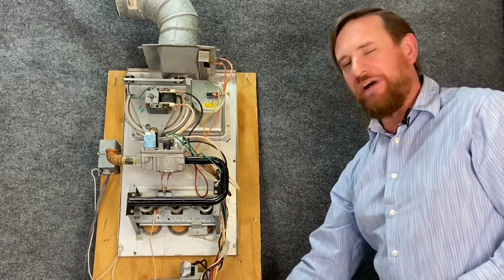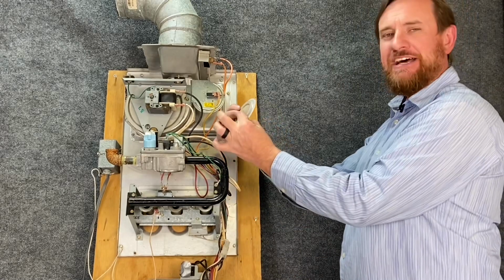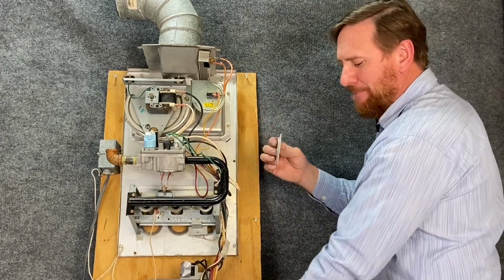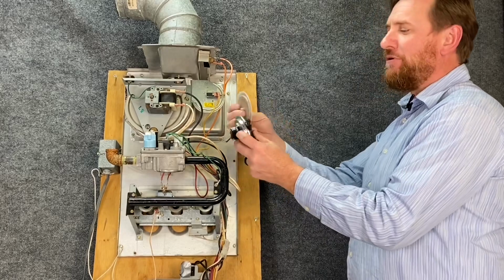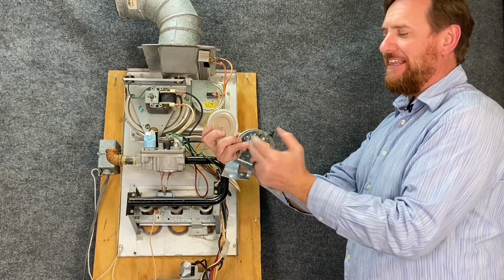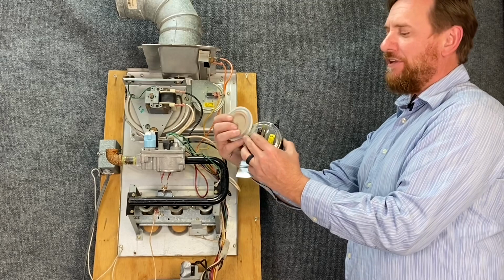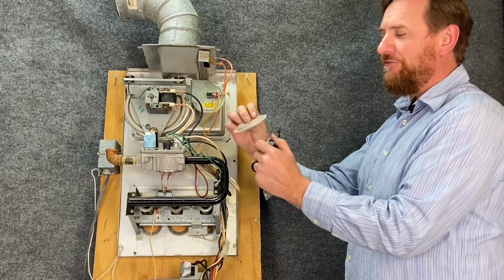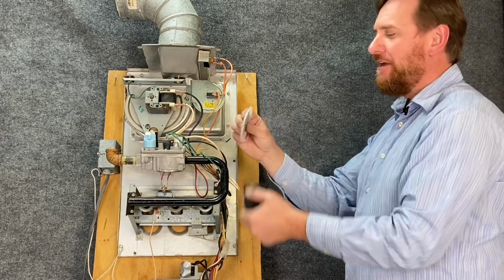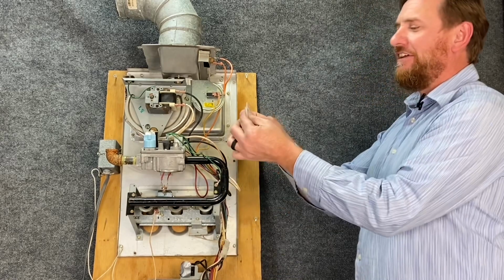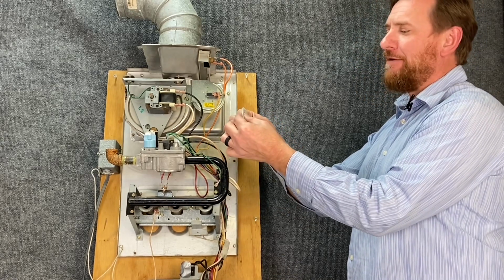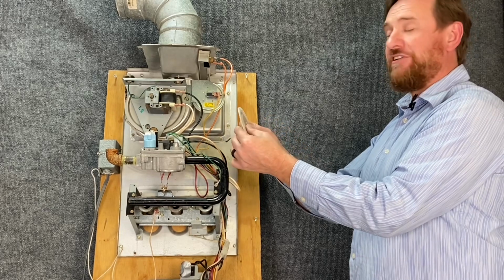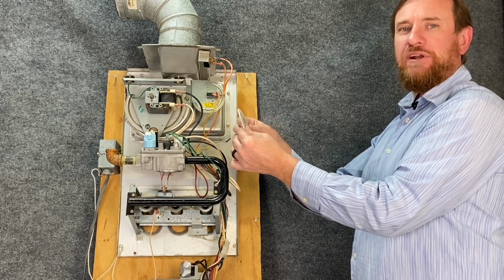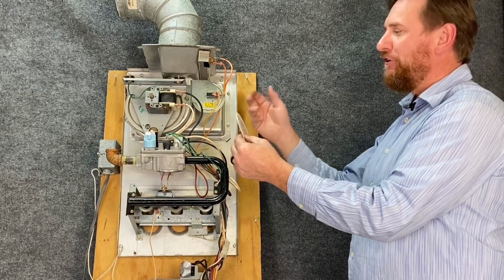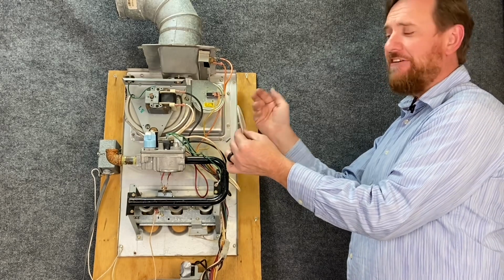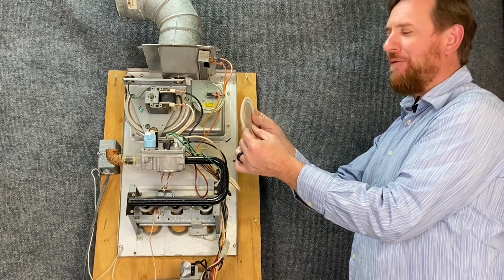So how it works is quite simple. Inside, there's a type of diaphragm, and there's also a micro switch on one side. When we pull a vacuum on one side, the atmospheric pressure pushes on the other. What it does is make the switch close. It physically moves the contact with this piece here. But this diaphragm is very fragile, a very thin type of material, so it's very easy to break. Over time, they can break or get worn out. They can crack and become brittle, especially if you have condensation in there, which you shouldn't have. That can build up in here and cause severe problems.